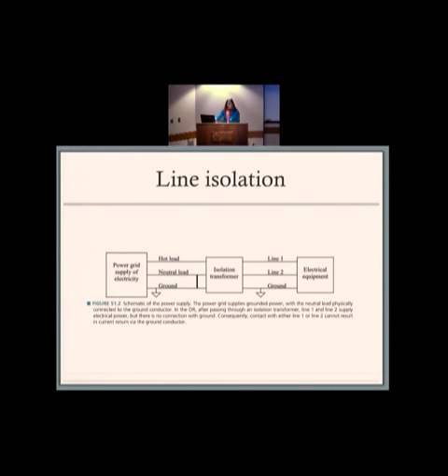In the OR you have this thing called an isolation transformer. It's really complicated, I'm trying to make it not complicated, but essentially line 1 and line 2 with the isolation transformer don't have a ground. So even if there was a leak or something... the bottom line is it's isolated from the mains power. Yes, line isolation.